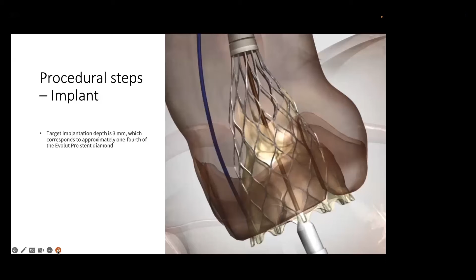And then as you deploy it more, your blood pressure will fall. That's the point where you want to unsheath it more rapidly and then get to the 2/3 deployment, at which point the valve is mostly functional and your blood pressure should come up. This is the time when you pause and you reassess the valve. The catheter has this inbuilt mechanism. You get this loud grating noise when you reach 2/3. So when you get to that point, you slow down and pressure comes up, then you stop.